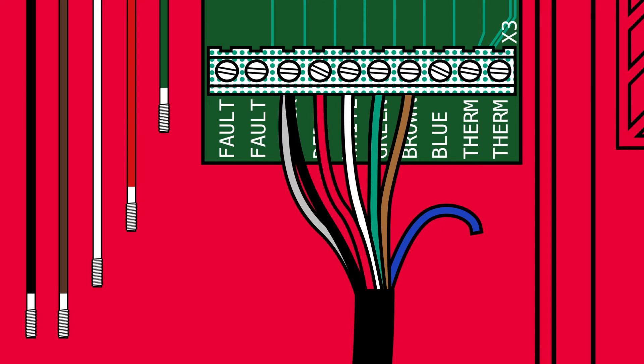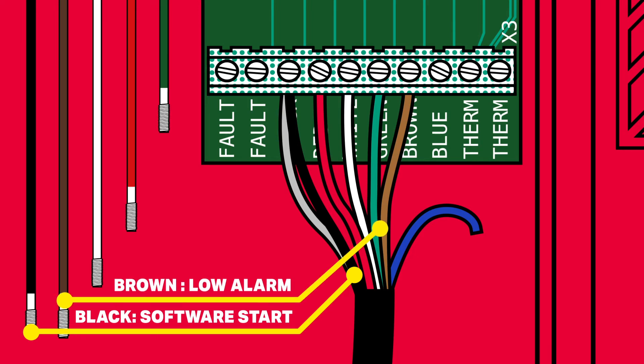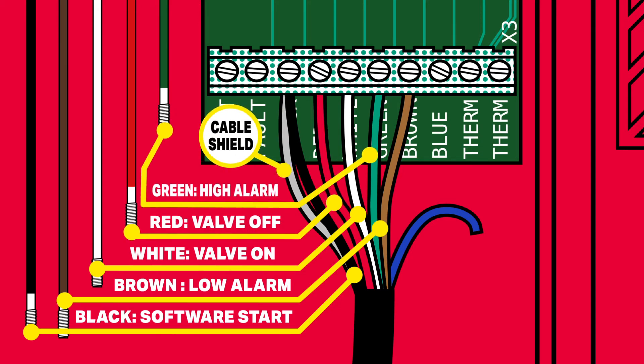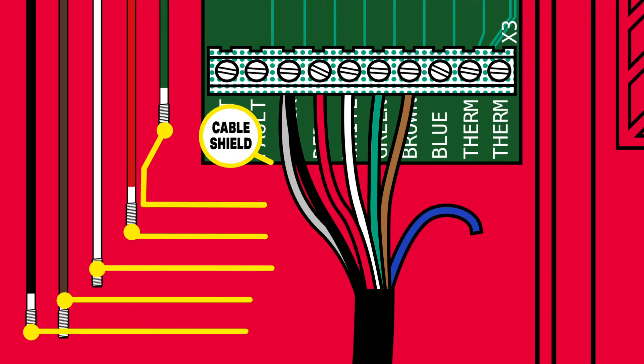From the longest rod to the shortest, the black is the software start switch and needs to be long or longer than the brown rod. The brown is the low alarm. The white turns the valve on. The red turns the valve off. And the green is the high alarm. The bare wire cable shield connects in with the black sensor wire.